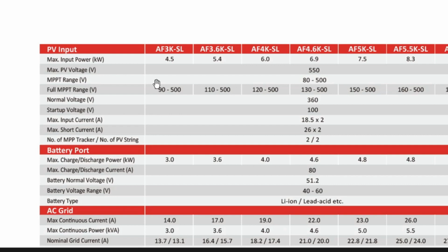One is the inverter's maximum DC voltage, for the split panel, and we also provide the full MPPT range. That means within this range, the inverter can do maximum power point tracking more efficiently, and can also reach its rated power fully. So when you design the string voltage, do not go past this upper limit, and it's better to be inside this range.